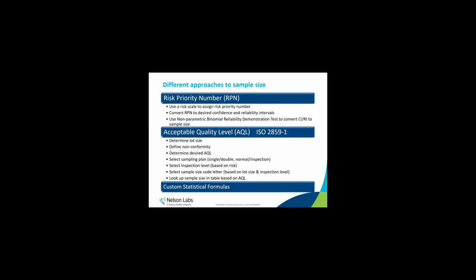If the risk of that nonconformance is low, meaning if you do have a nonconformance, it isn't the end of the world, then you can have a higher AQL, like a defect rate of 1 in 100. If the failure would pose a high risk to patient safety, then you're going to need to get that AQL as low as possible, maybe 1 in a million. Now you pick the sampling plan table from the list that's most appropriate for you. Then you pick an appropriate inspection level based on the amount of risk you can tolerate. Both these selections should be justified and explained. And then you use the lot size and inspection level to get a sample code letter and match that to the sample plan table. And voila, you take your AQL and you come up with a sample size.